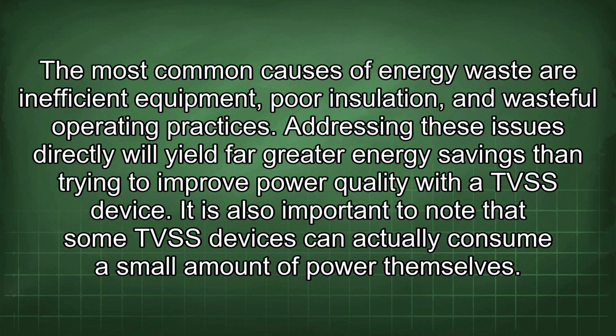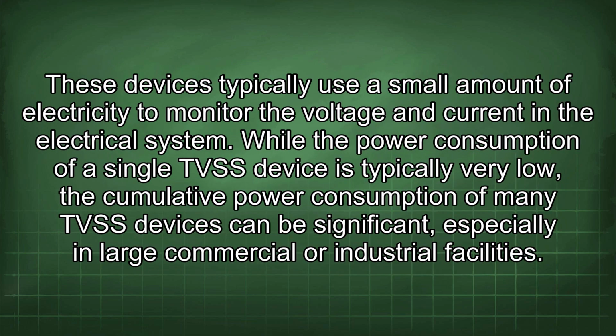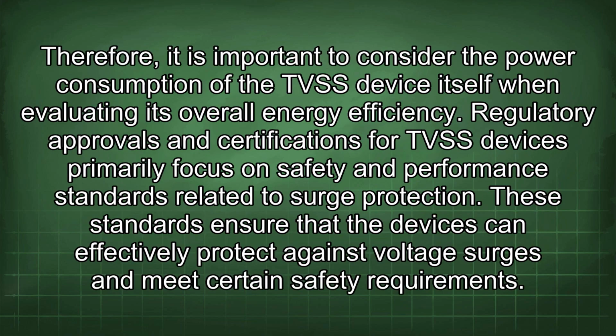It is also important to note that some TVSS devices can actually consume a small amount of power themselves. These devices typically use a small amount of electricity to monitor the voltage and current in the electrical system. While the power consumption of a single TVSS device is typically very low, the cumulative power consumption of many TVSS devices can be significant, especially in large commercial or industrial facilities. Therefore, it is important to consider the power consumption of the TVSS device itself when evaluating its overall energy efficiency.